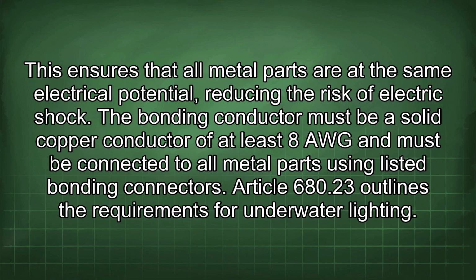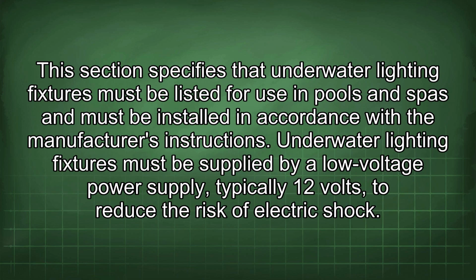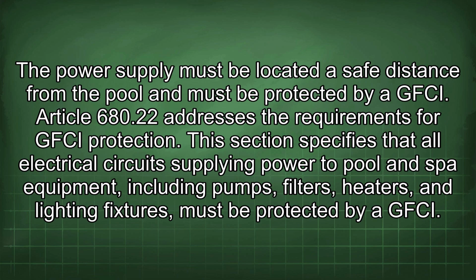Article 680.23 outlines the requirements for underwater lighting. This section specifies that underwater lighting fixtures must be listed for use in pools and spas and must be installed in accordance with the manufacturer's instructions. Underwater lighting fixtures must be supplied by a low voltage power supply, typically 12 volts, to reduce the risk of electric shock. The power supply must be located a safe distance from the pool and must be protected by a GFCI. Article 680.22 addresses the requirements for GFCI protection.